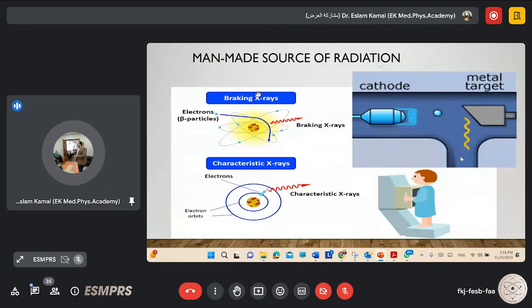So the X-ray photons which are produced from the X-ray tube will have high energy, and the number of photons which are produced from the X-ray tube will be higher. So by increasing the KV, you are going to increase the energy of the X-ray, and you are going to increase the number of photons produced from the X-ray tube.